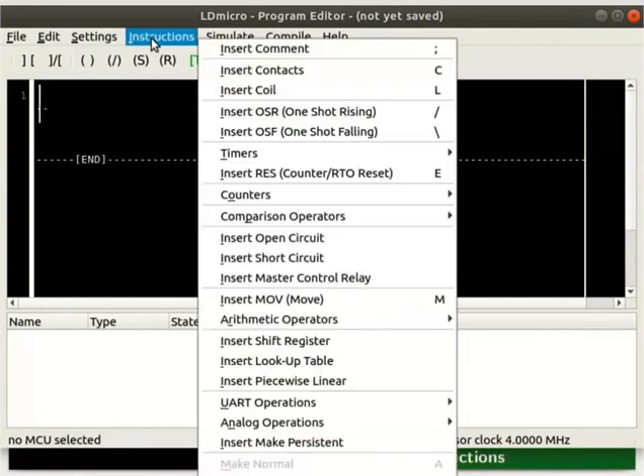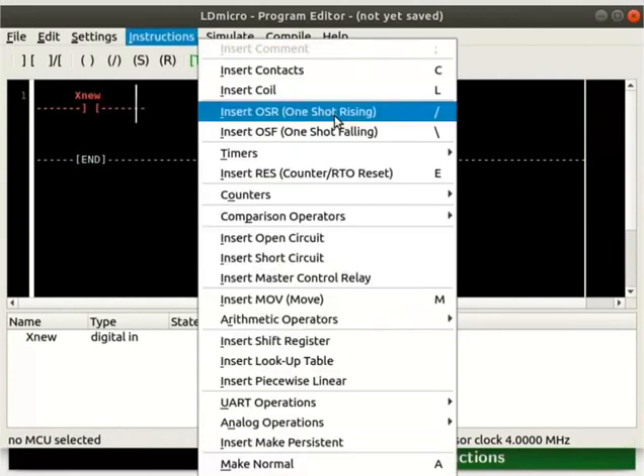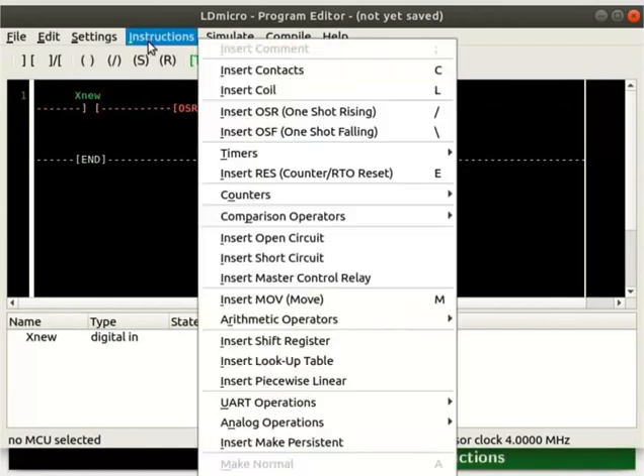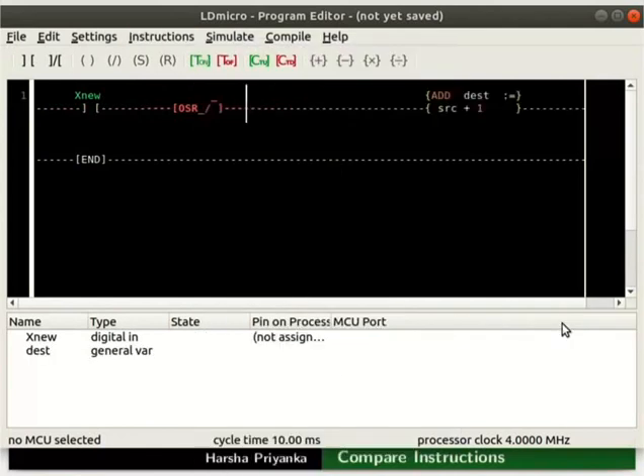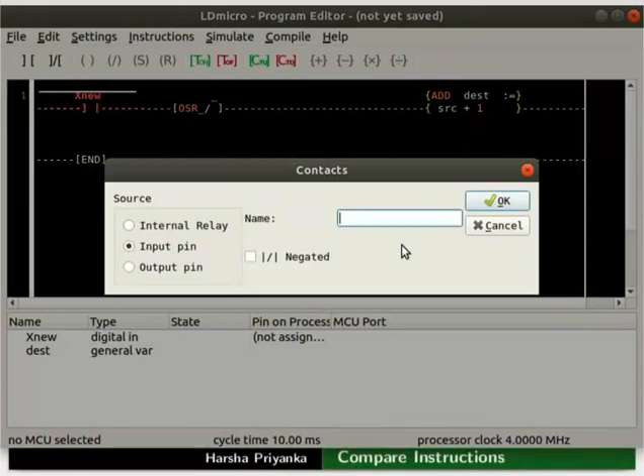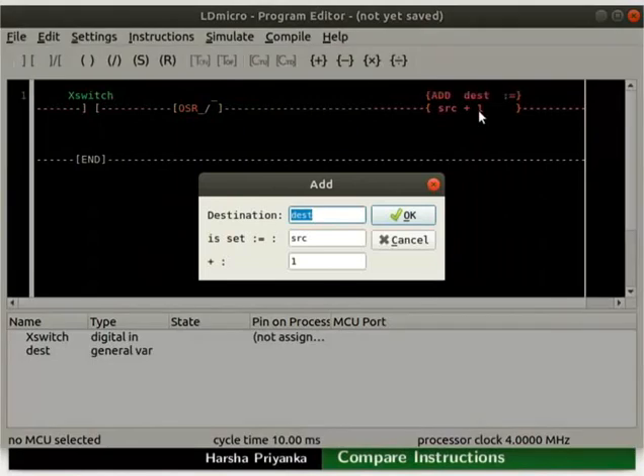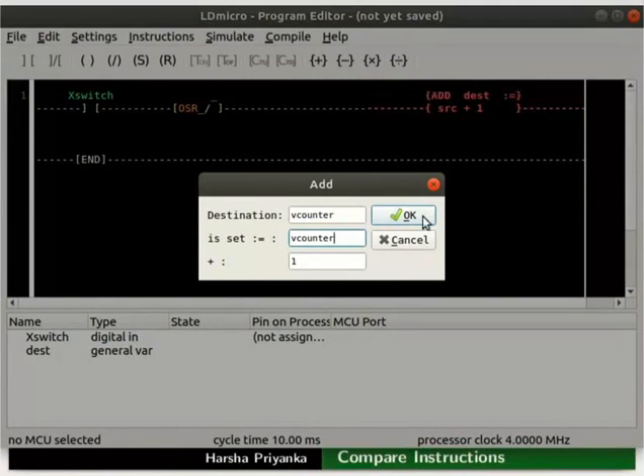Insert a contact. To the right of it, insert an OSR. To the right of OSR, insert an Add instruction as shown here. Rename the contact as Switch. Double click on the Add instruction. Set the destination and first operand to V-Counter, meaning Virtual Counter. The second operand is by default 1 — don't change that. Click the OK button.